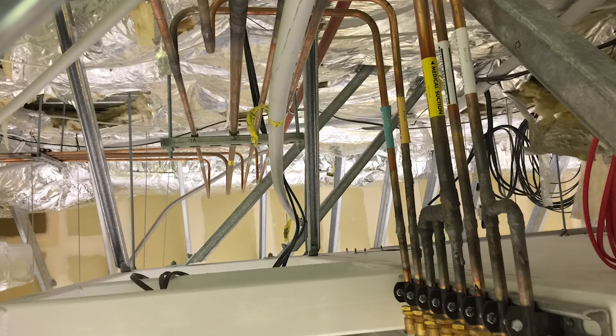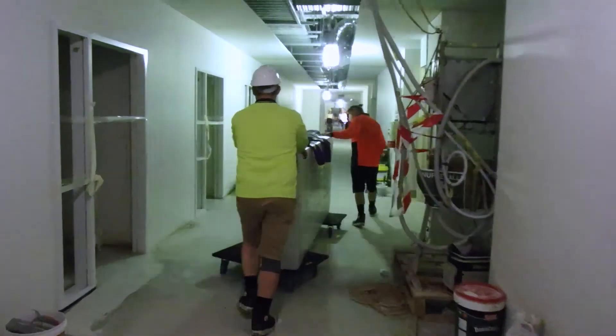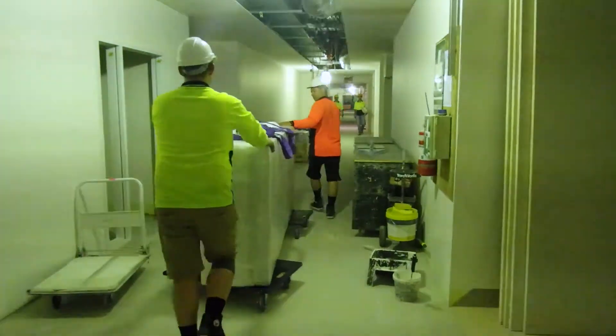With the integrated lighting, with the integrated connections for medical gas and ductwork, it means that on one day when you're installing in an operating theatre you have fewer trades trying to coordinate on site. That reduces the risk profile from an installation perspective.